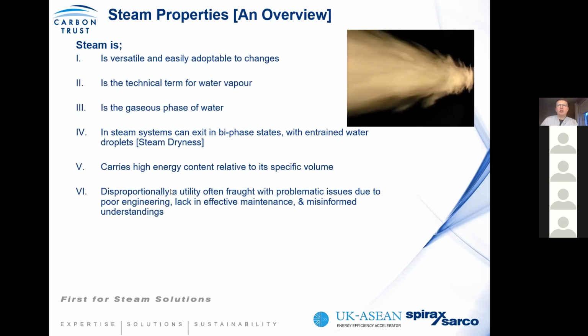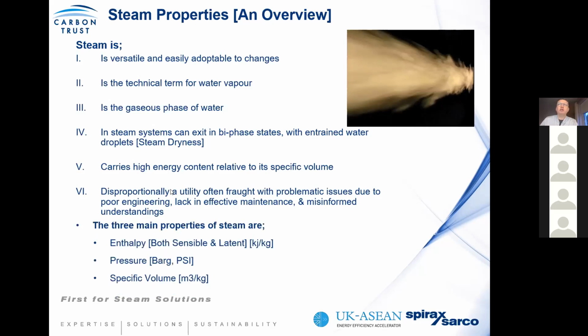So when we start talking about steam, we need to consider the three main properties. We have the enthalpy of steam, which is the energy. It's both sensible and latent. Sensible is where you heat water or gas, basically by increasing its temperature without a phase change. Latent energy, which is the highest part of the energy content of steam, is where you're changing its phase or state, i.e., from a vapor back to a water. And that's what steam wants to do.